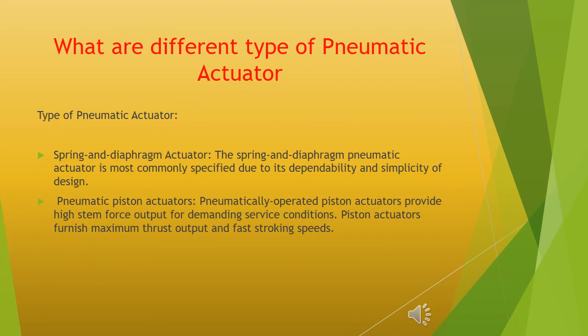What are the different types of pneumatic actuators? Types of pneumatic actuators: Spring and diaphragm actuator — the spring and diaphragm pneumatic actuator is the most commonly specified due to its dependability and simplicity of design. Pneumatic piston actuators — pneumatically operated piston actuators provide high stem force output for demanding service conditions; piston actuators furnish maximum thrust output and fast stroking speeds.